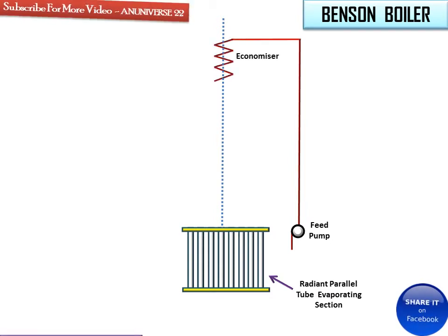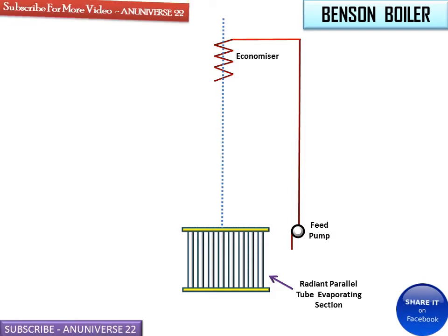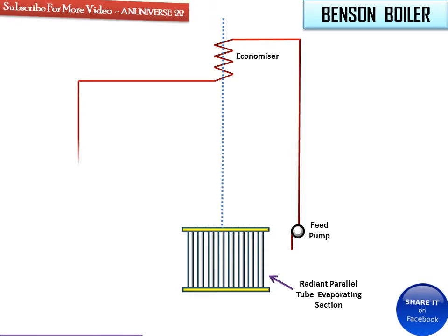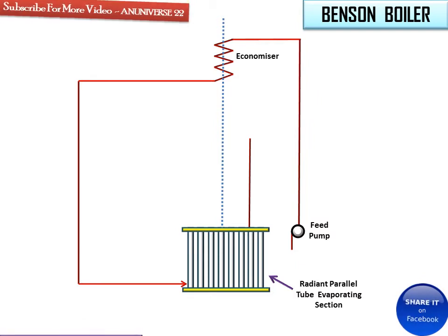This is the economizer. Water from the feed pump enters into the tube which first passes through the economizer, which uses combustion gases to preheat the water, and which also increases the efficiency of the boiler. From the economizer, this hot water is supplied to the radiant tube evaporating section, where the majority of the water is converted into steam.